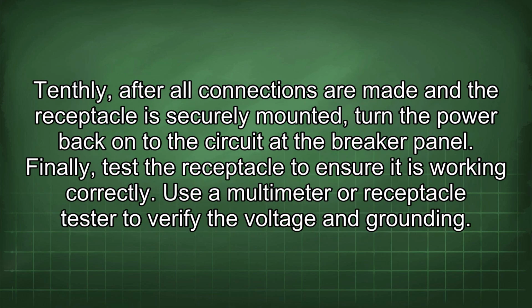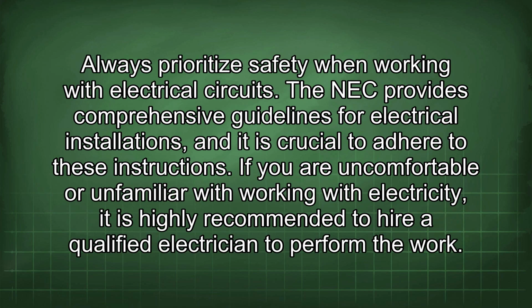Tenthly, after all connections are made and the receptacle is securely mounted, turn the power back on to the circuit at the breaker panel. Finally, test the receptacle to ensure it is working correctly. Use a multimeter or receptacle tester to verify the voltage and grounding. Always prioritize safety when working with electrical circuits.